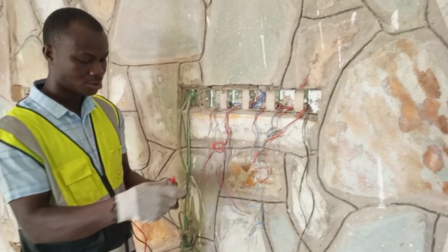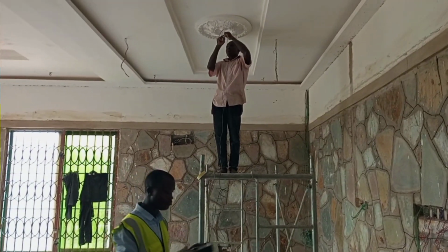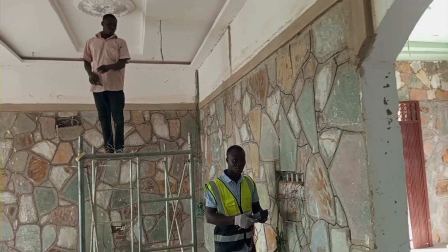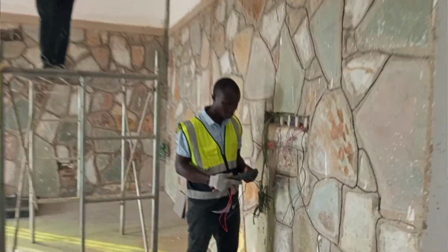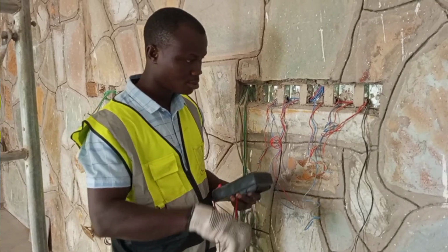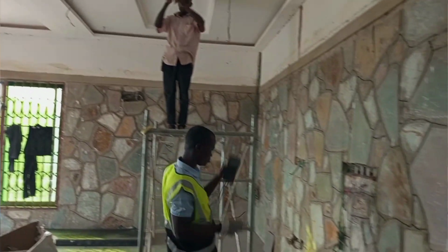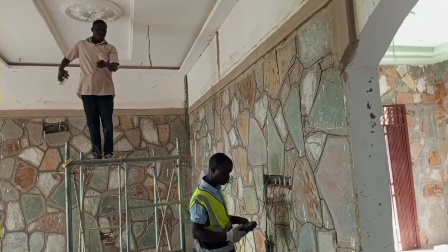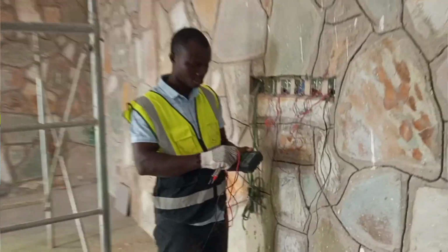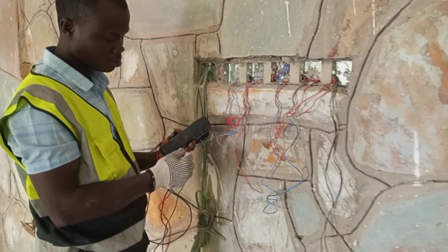Now, if you do the test and the wire is continuous, then that tells you that that particular wire is the switch wire for that particular lighting point. So here we are doing a test. We don't know which of these wires is going to the top there. So we'll attach an extension to the end of the switch wire at the lighting point up there, and then bring it closer to the switch box. So we'll check all the wires in these switch boxes just to be able to identify which of them is going to that particular lighting point.